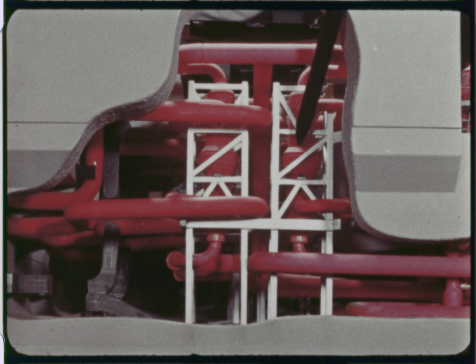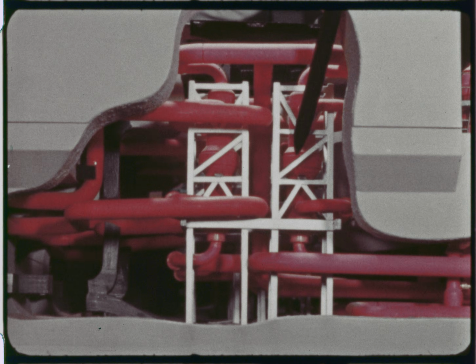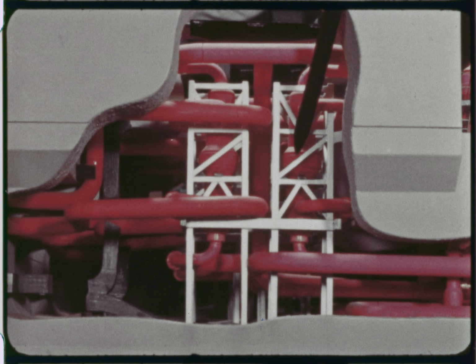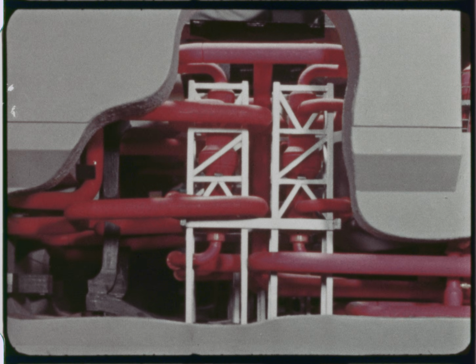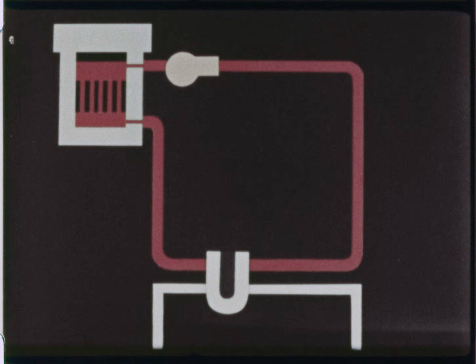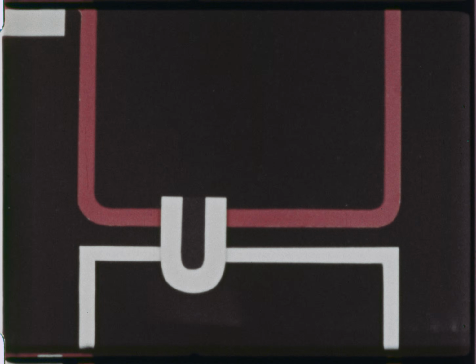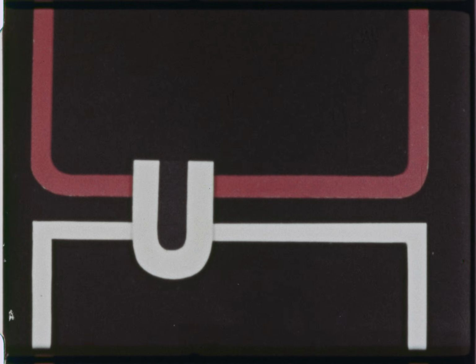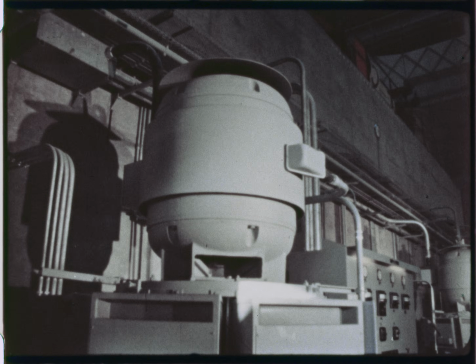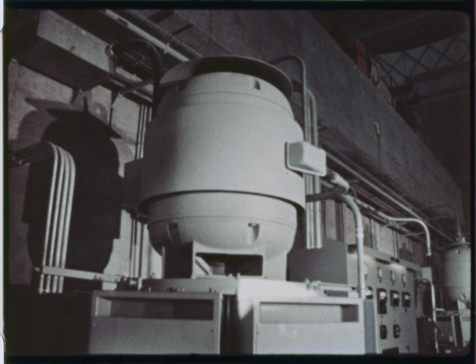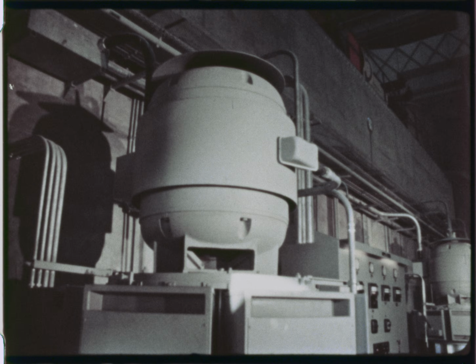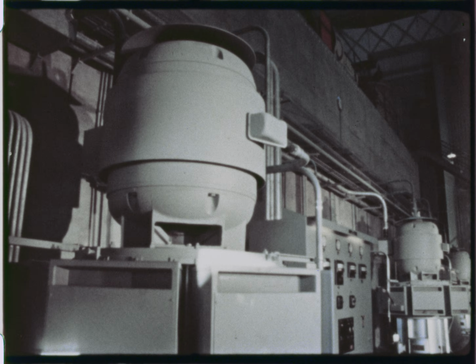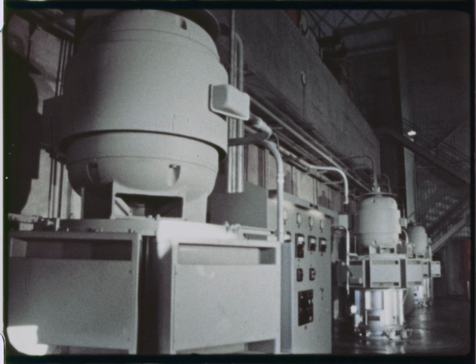Thermal expansion is provided by a bellows mounted in the straight shell section and permits solid construction of the tubes containing the radioactive sodium. In the intermediate heat exchanger, the secondary loop of non-radioactive sodium is heated by the primary sodium to 895 degrees Fahrenheit. The hot sodium is pumped by centrifugal pumps to the 3 steam generators. These pumps are similar to those used in oil refineries.